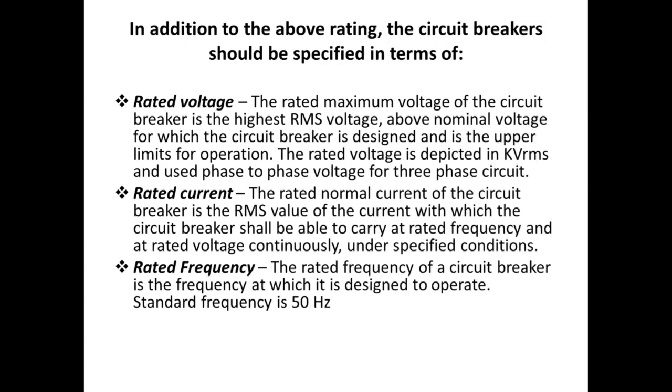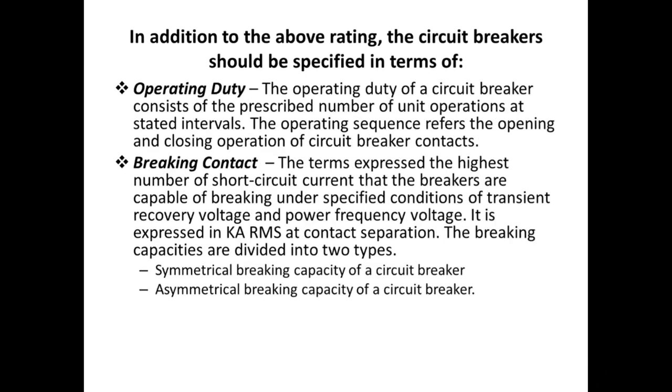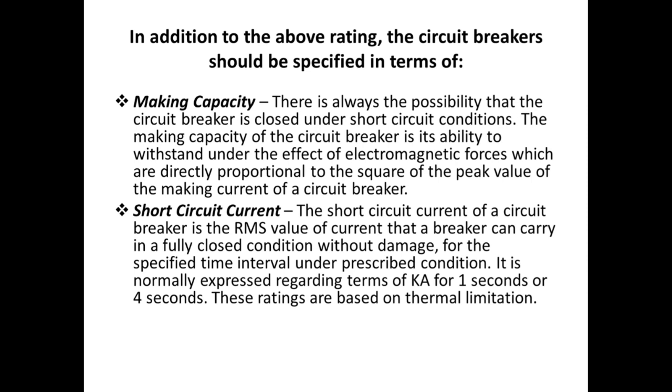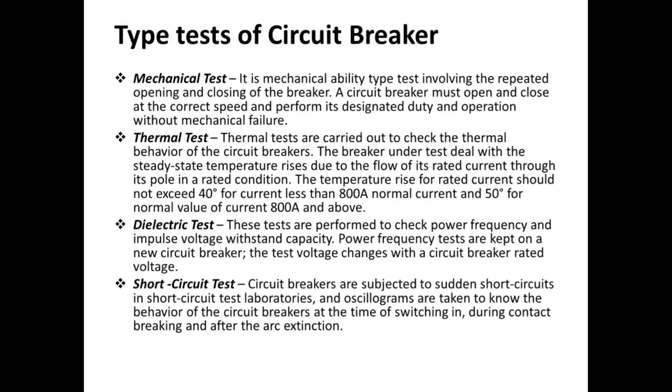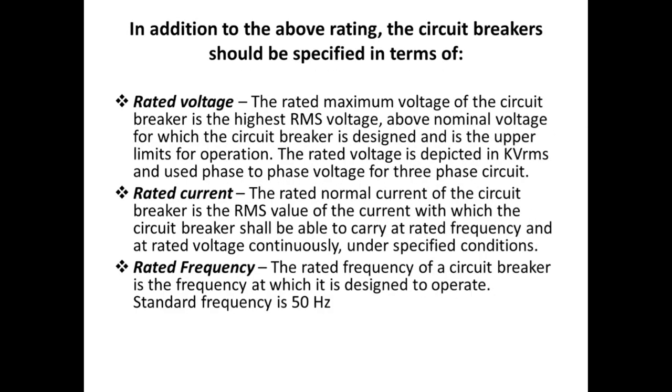So next, in addition to the above rating, the circuit breaker should be specified in terms of rated voltage, rated current, rated frequency, and operating duty, breaking capacity, making capacity and short circuit current. So back to the rated voltage. So what is rated voltage?